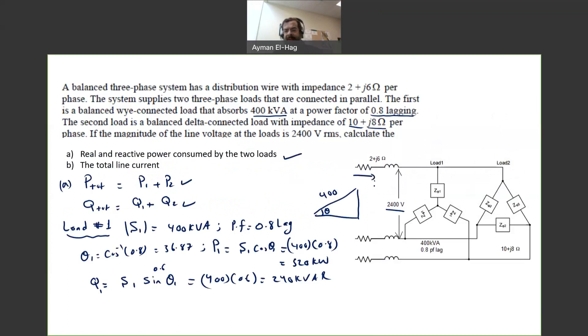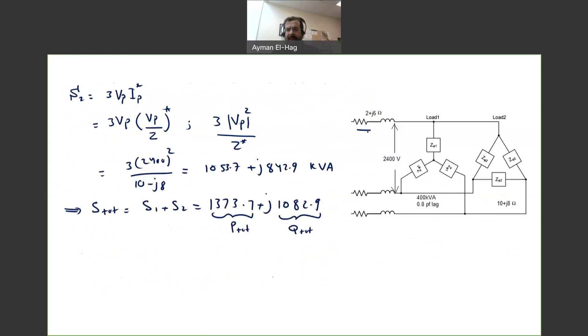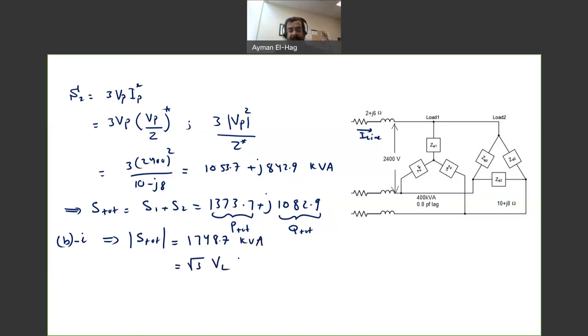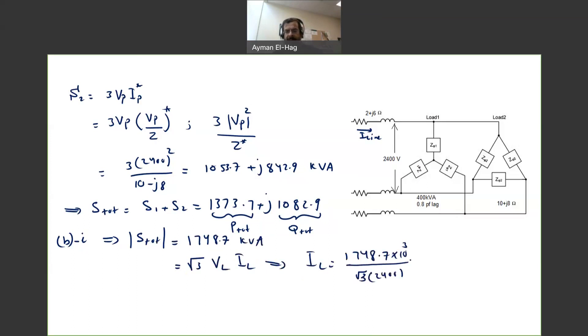The second requirement is to find the line current I line. The first approach — the safe approach — uses S total. The magnitude of S total is 1748.7 kVA. Since S total equals root 3 times V line times I line, I line equals 1748.7 times 10³ divided by root 3 times 2400, which gives 420.7 amps.